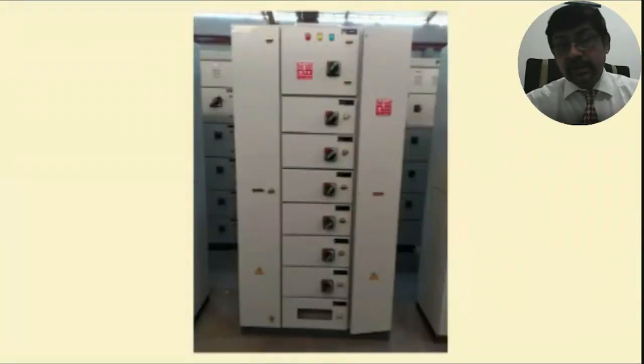Yes, next. This is the panel. This is basically a distribution board panel in the industry. When the generator power comes, the cables coming out of the generator are connected here in this panel. From this panel, the distribution goes to different sections or different loads, whether it is an AC load or a motor load, or if it's a mall, then level one, level two, and so on. On the left and right, you can see one is the busbar chamber and one is the cable alley, meaning one has the busbar and incoming, and the other is the outgoing cable alley.